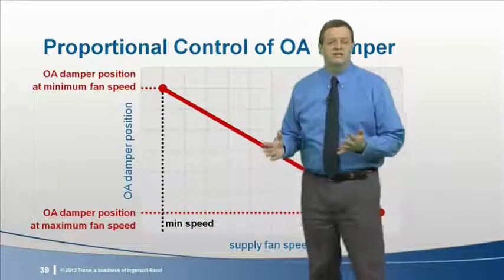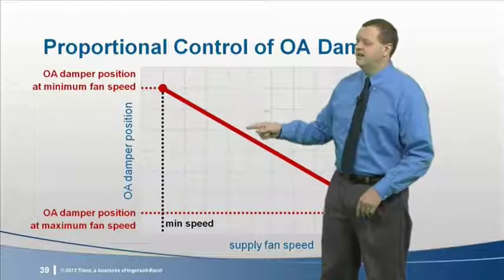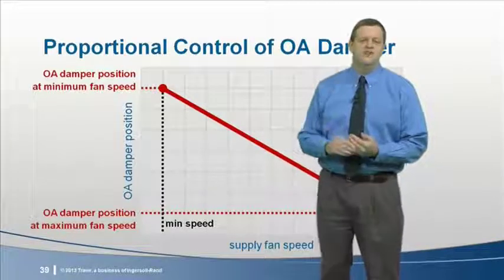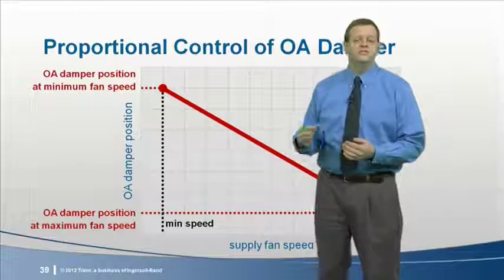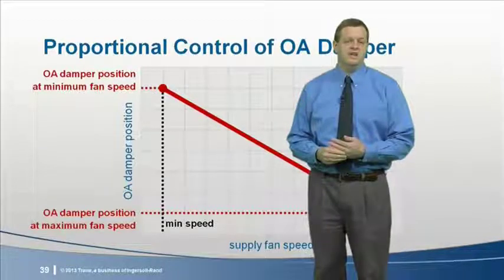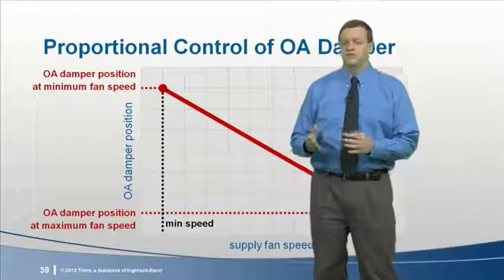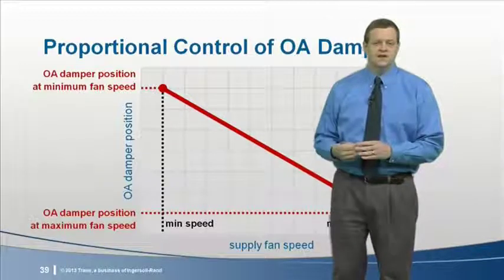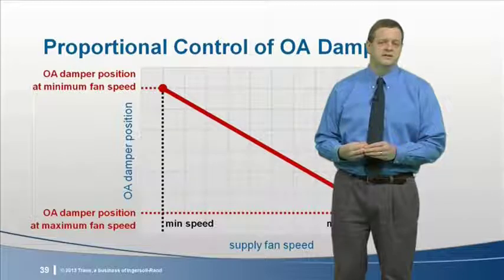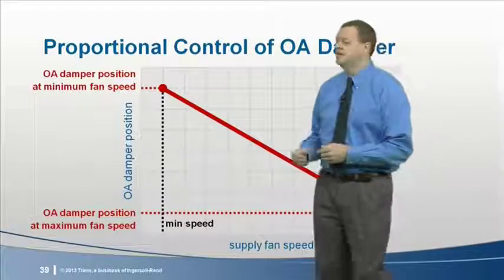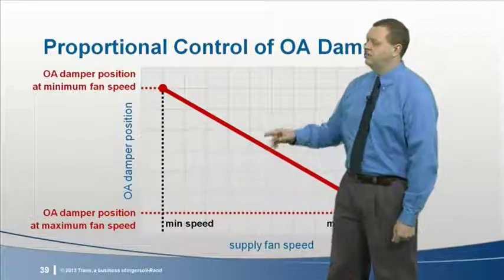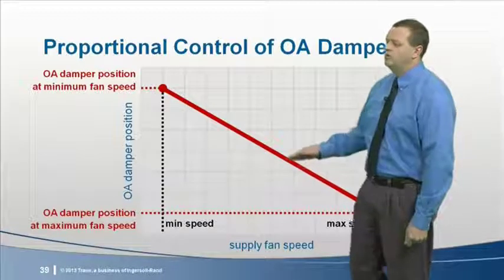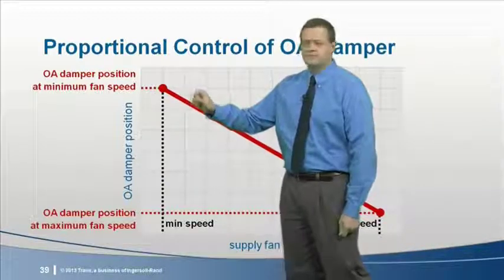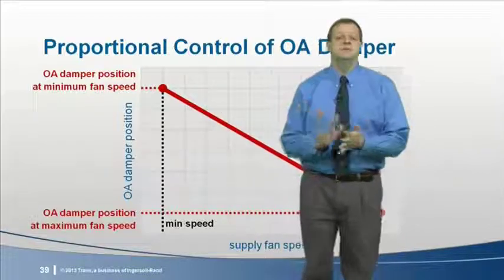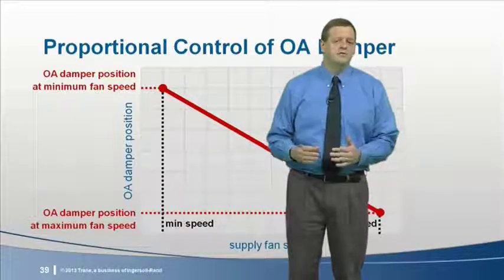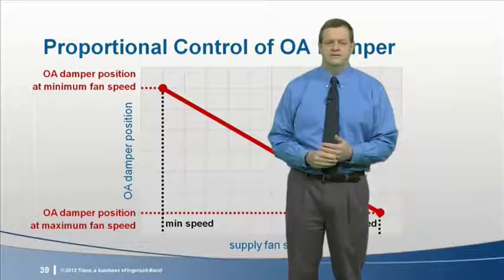During system operation, the controller modulates the position of this outdoor air damper in proportion to the change in supply airflow, which is determined from the signal sent to the variable speed drive on the fan. So the controller first adjusts fan speed, like I described in the variable speed fan control sequence. Then, using that current speed, the outdoor air damper position is modulated according to this proportional relationship, opening further as fan speed is reduced. Again, this is the minimum damper position. It may be opened further when conditions are suitable for economizing.